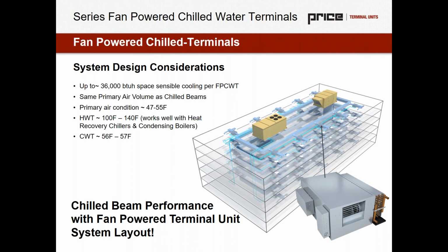For our fan powered chilled water terminals, we're seeing up to 36 MBH of space sensible cooling as a maximum for a fan powered chilled water terminal. We're seeing the same primary air volume as chilled beams, so 1/4 of traditional VAV systems on average. We're seeing the same kind of water temperatures, so that 100 to 140 degree heating water temperature is very typical, and that elevated sensible only chilled water temperature of 56 or 57. And we're seeing a primary air condition, once again, usually centered around that 55 degree primary supply, although for higher humidity applications, that's driven down pretty commonly in our system as well, where we can get as low as 47 to provide a greater latent supply to the space.